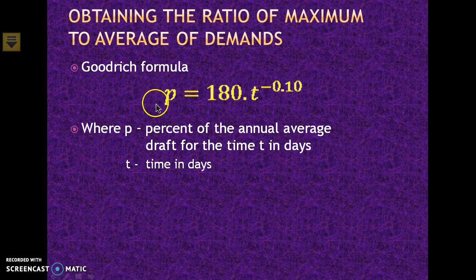You see, the ratio of the maximum demand to the average demand is obtained by multiplying 180 to the time, which is represented in days and has a power of minus 0.10. So, if it is a daily demand, your time variation is 1. If it is a monthly demand, your time variation is 30. By substituting the respective t values, you can obtain the ratio of maximum to average demands.